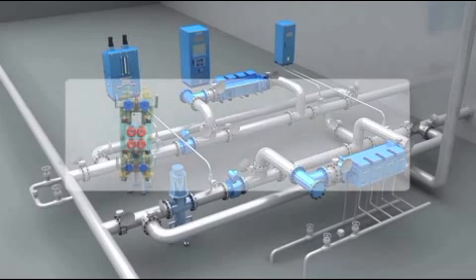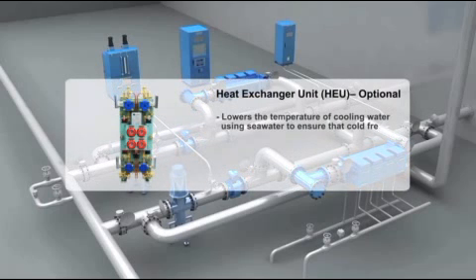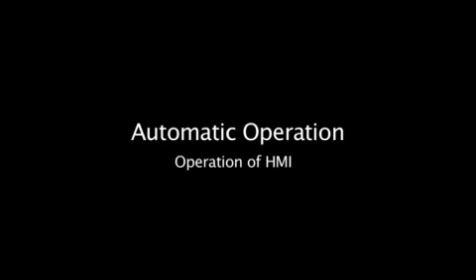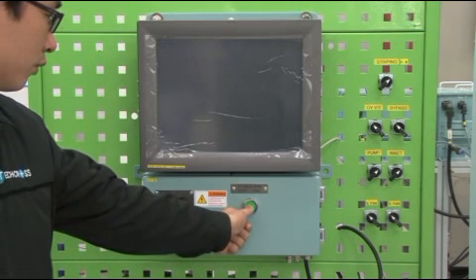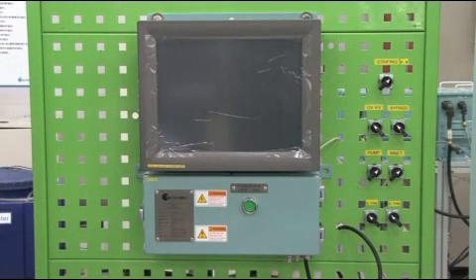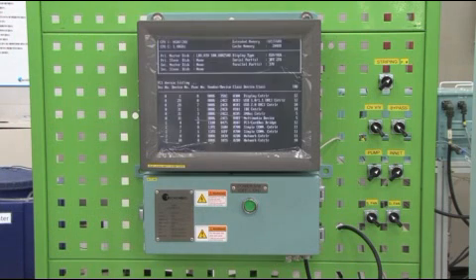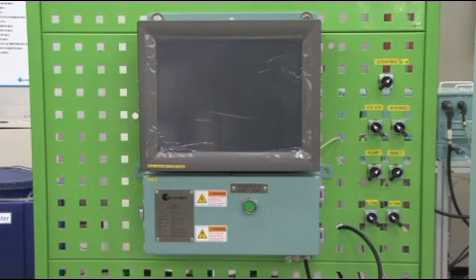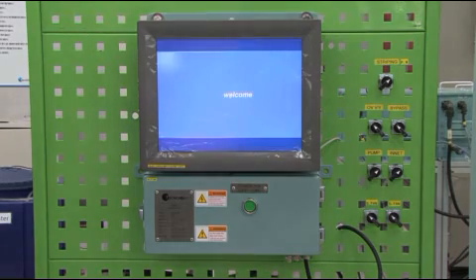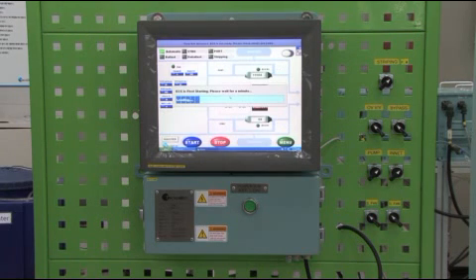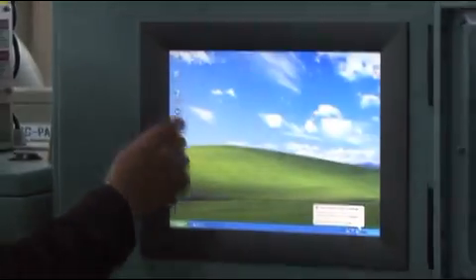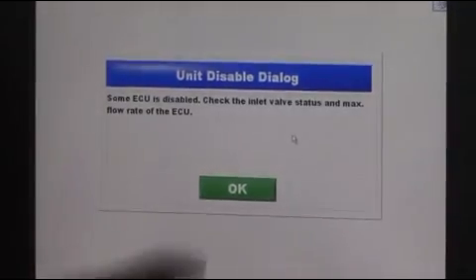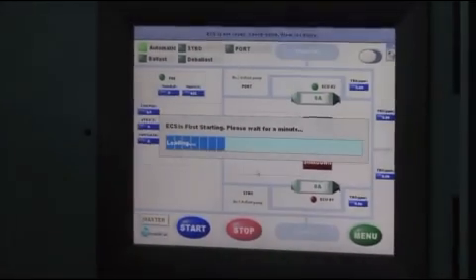Heat exchanger unit, HEU, optional. It lowers the temperature of cooling water using seawater to ensure that cold fresh water is supplied to the rectifiers. Automatic operation. 1. Operation of HMI. Step 1. Master CPC. The HMI is designed to start automatically when the power of Master CPC is on. Step 2. Slave CPC. The HMI of Slave CPC is not designed to start automatically, unlike the HMI of Master CPC. Click to start the HMI of Slave CPC in the front part of PDE.